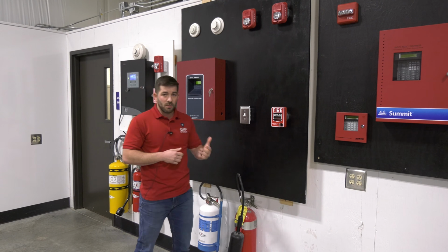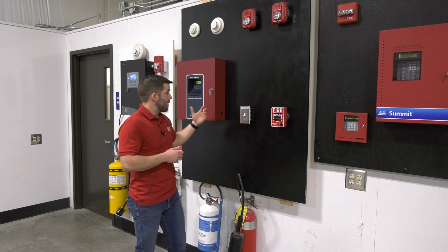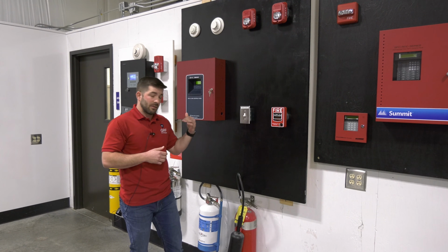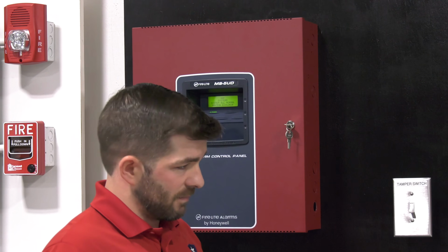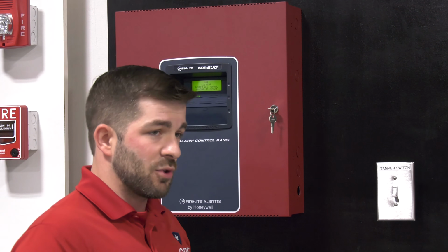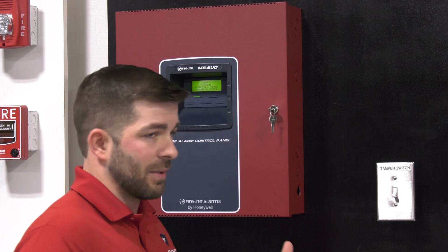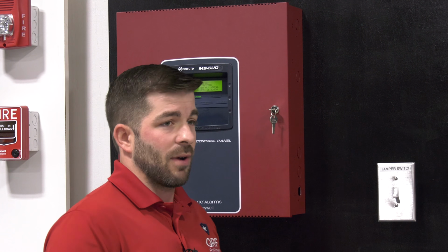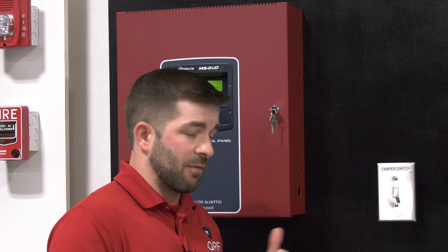Now you do have newer panels that have IP communicators directly on the panel. Like I said in my class, I highly, highly recommend, if you use IP, to use it as your primary means of communication, not your backup. By code, each panel has to have two means of communication. You have your primary and your secondary. Your secondary is used for when the primary fails. Being IP and being over a data network, if it goes down, you don't want that to be your backup. Your backup needs to be your fail-safe.